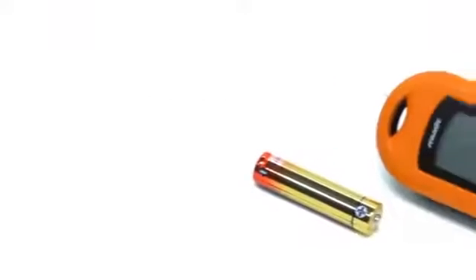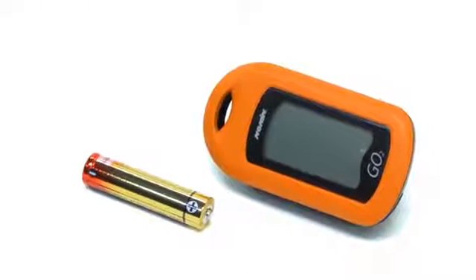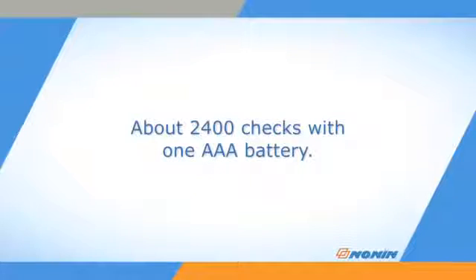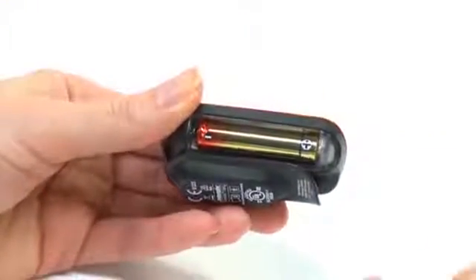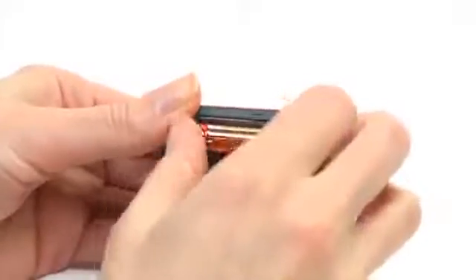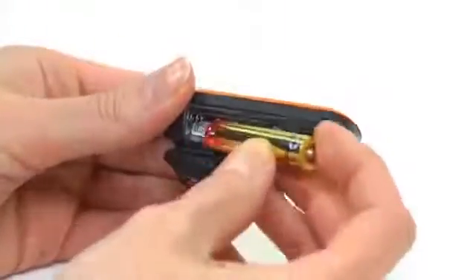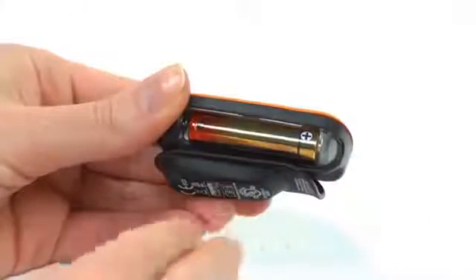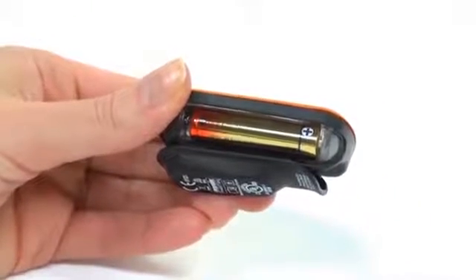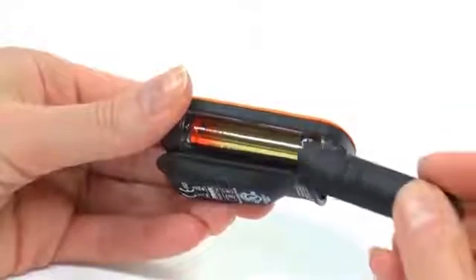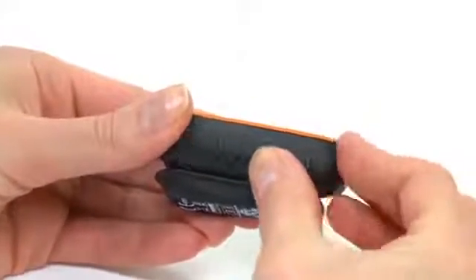The GO² oximeter uses a single AAA battery for power. Each fully charged battery will perform about 2,400 spot checks with the GO² oximeter. Battery changes are easy. Simply slide off the battery door and remove the old battery. Insert a fresh AAA battery matching the positive and negative contacts to the markings in the battery compartment. Replace the battery door and you're ready to use the oximeter.